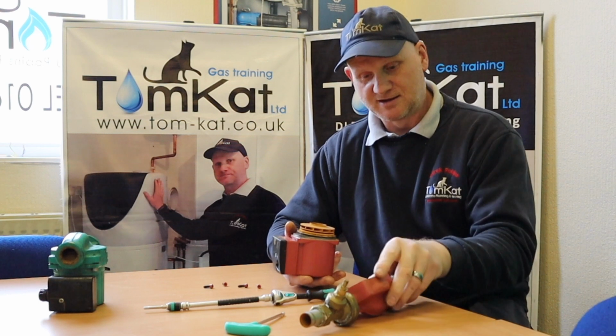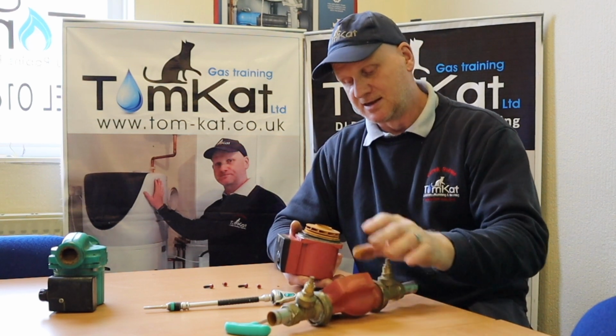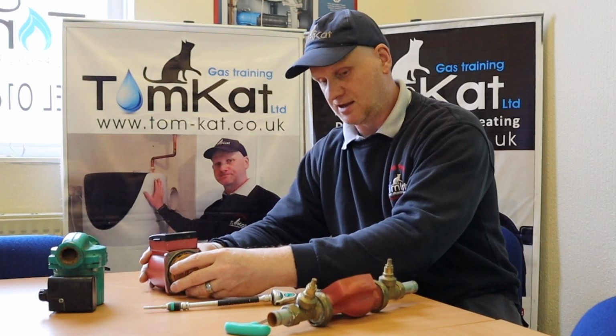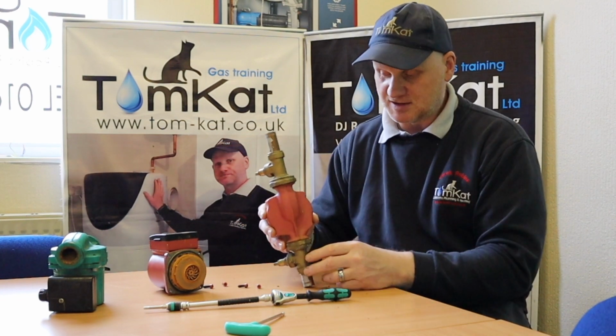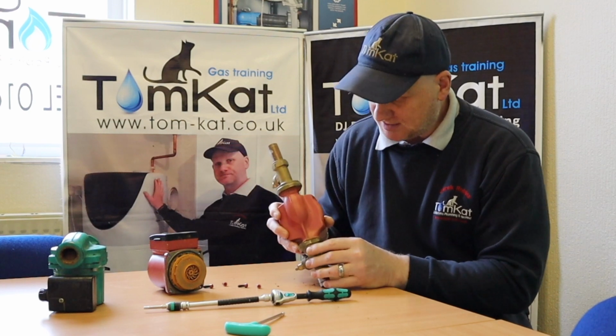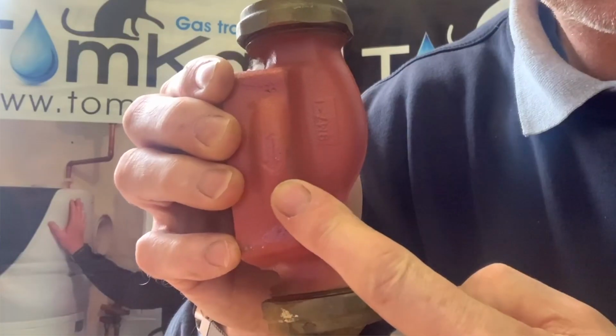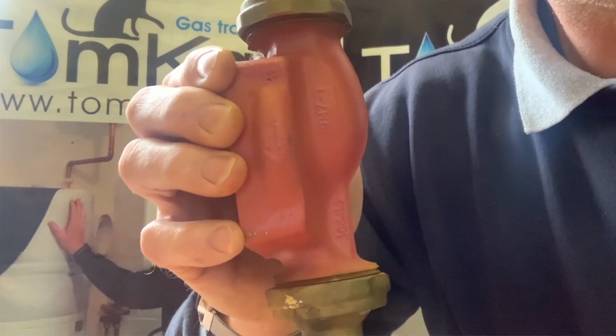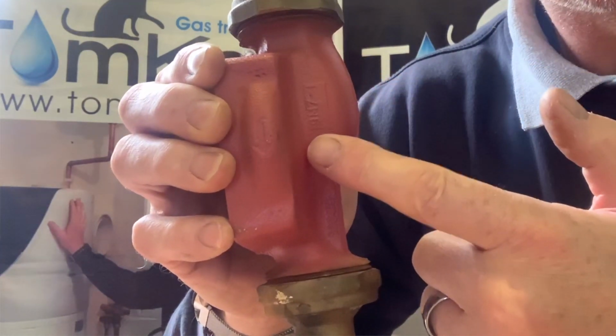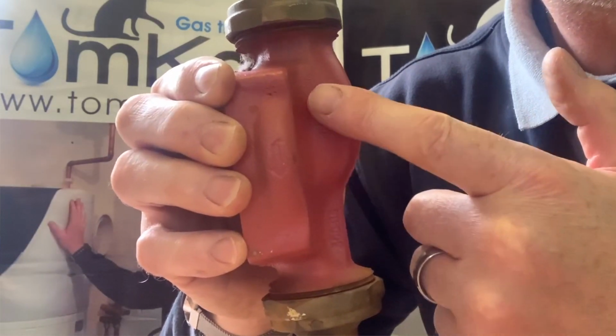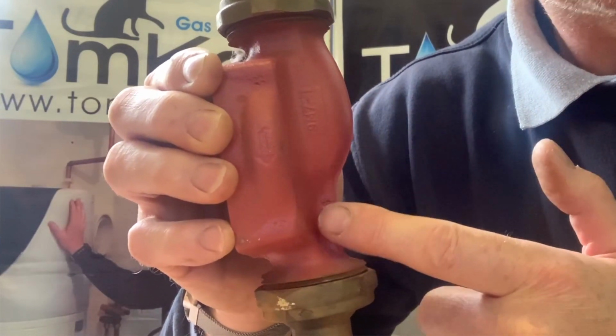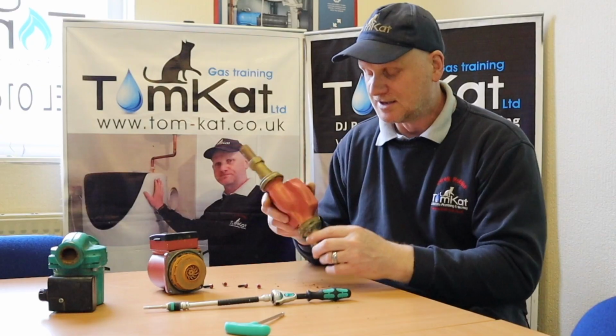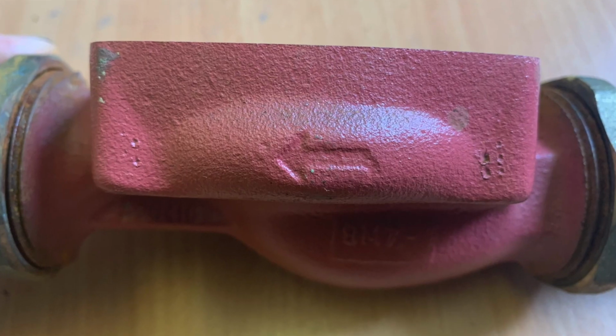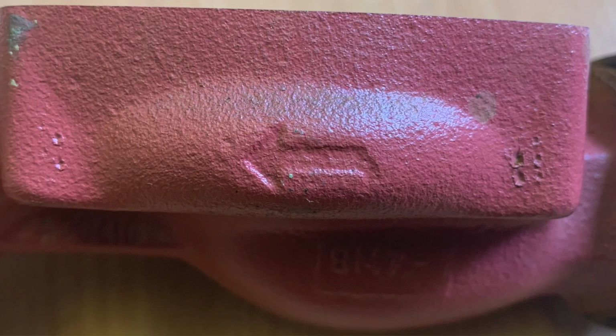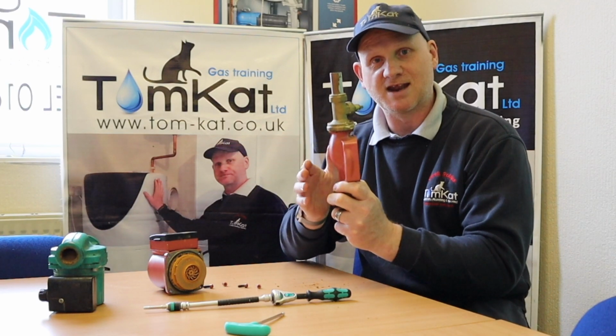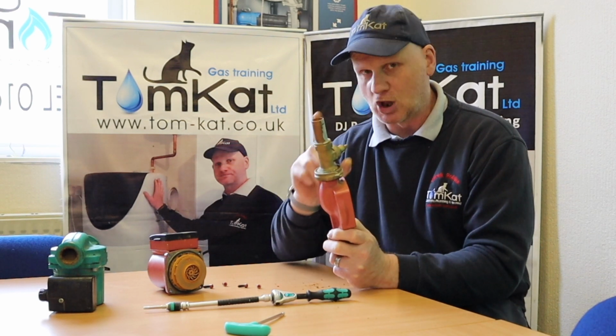You can see it's a bit rusty inside. Now then, let's look at the body first. The first thing you can see is there is an in and an out, and we can tell this by the flow arrow here. But another way you can tell which is the in and which is the out is this bulge here. It's where the water comes into the bottom of the impeller, and where there isn't a bulge, it's where it goes out. So you can see there is an arrow on there, but if you can't read that arrow, then the bulge will tell you exactly which is the in and out and which way the pump is pumping. It will only pump one way.